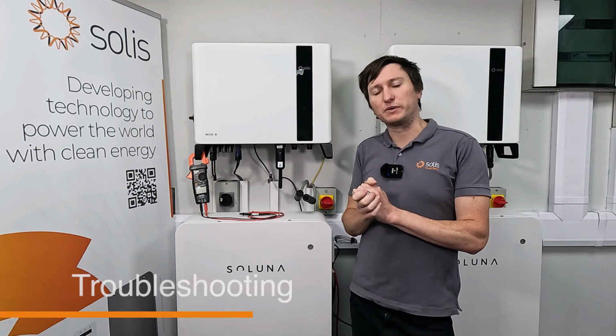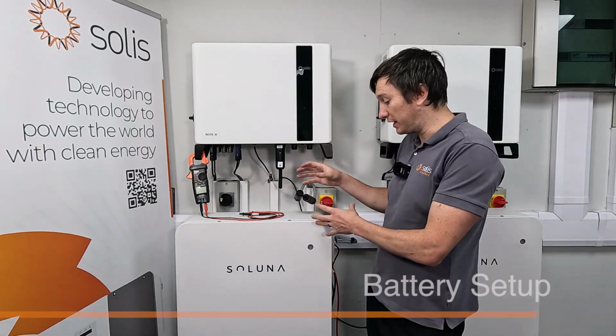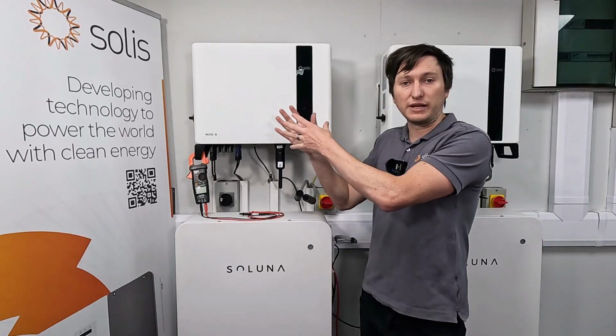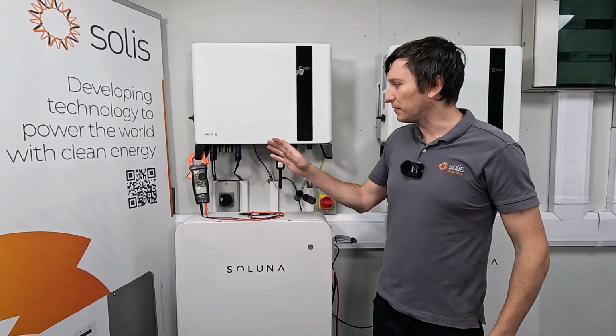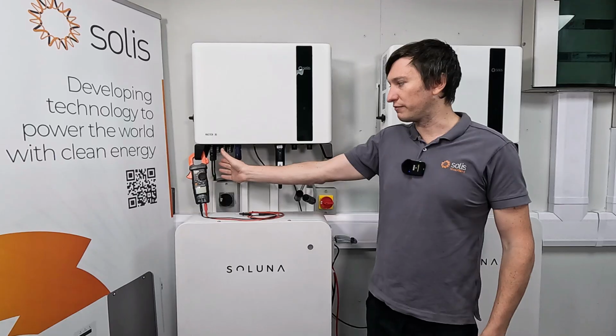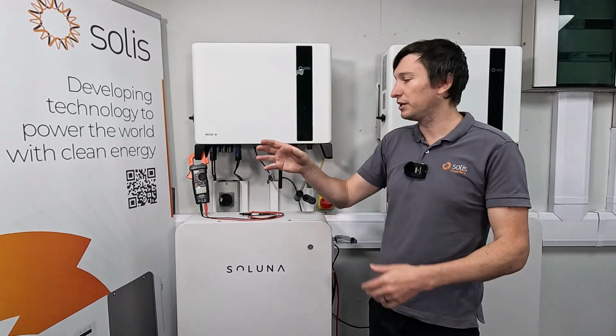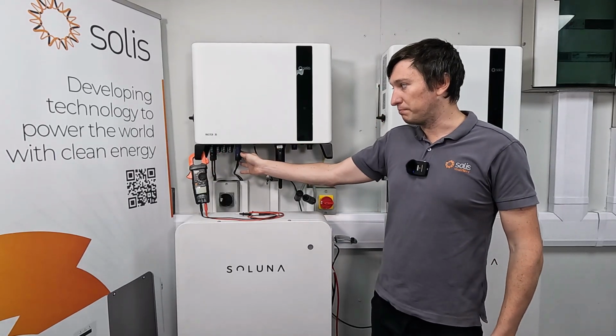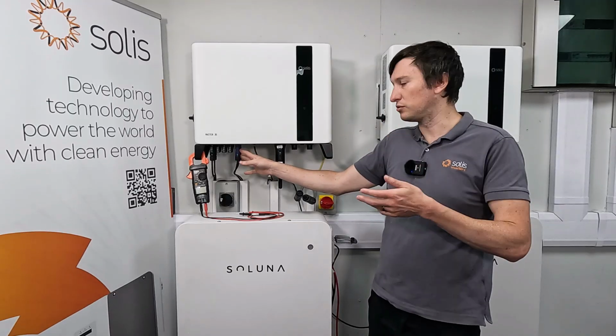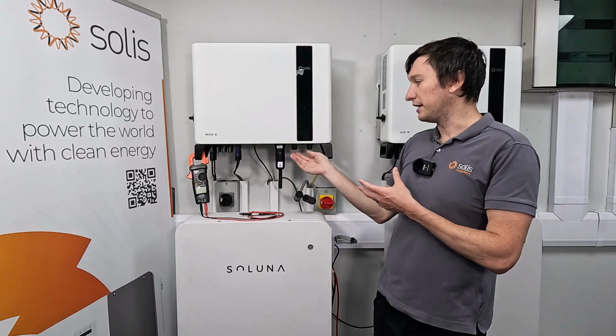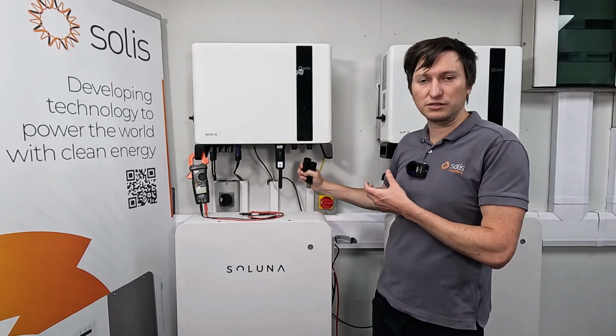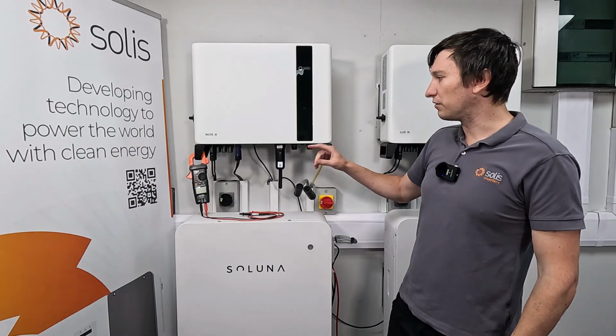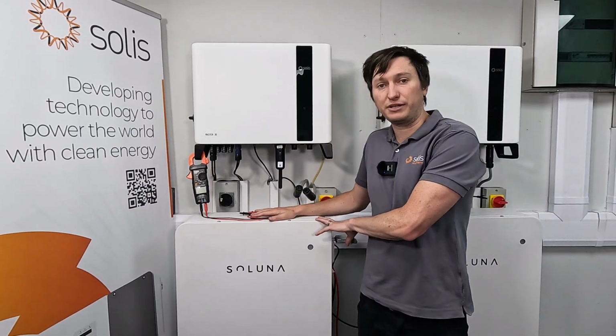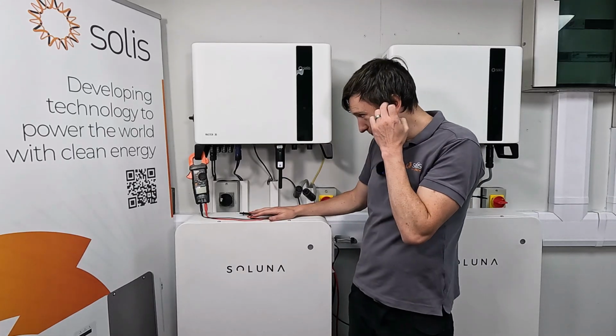The next interface we're going to set up is the battery power connections, turning on the battery to interface with the inverter. There are 3 power supplies in this inverter: one for the solar, which should turn it on like earlier; one for the batteries, which when given voltage above 200 volts should turn on the inverter and give indications here; and the last power supply is the grid connection, which when given grid voltage should also turn on the inverter. So we're now going to turn on the batteries, and we should see power here.